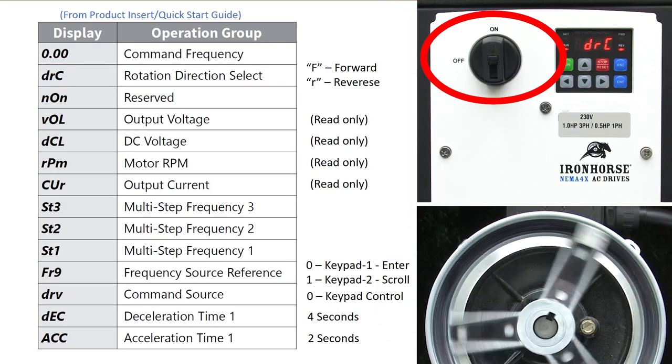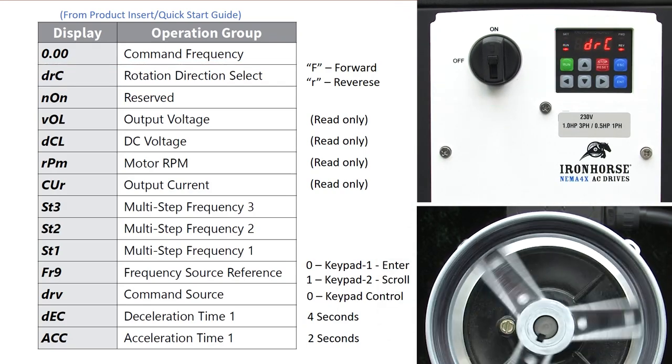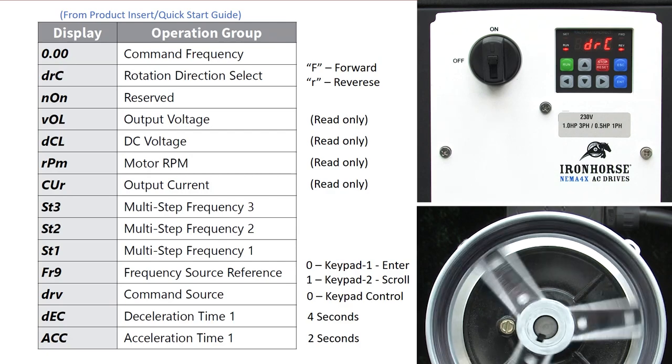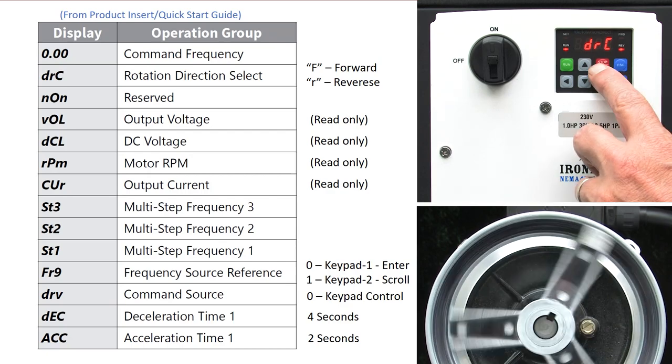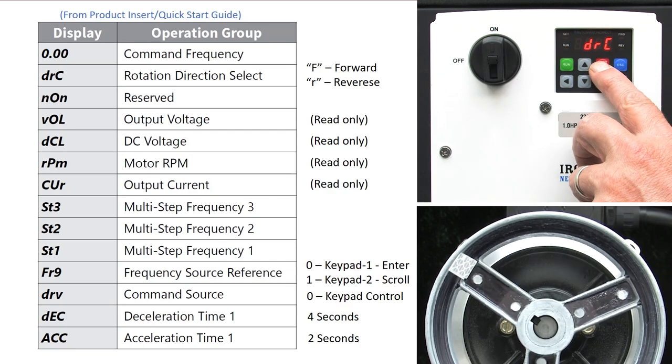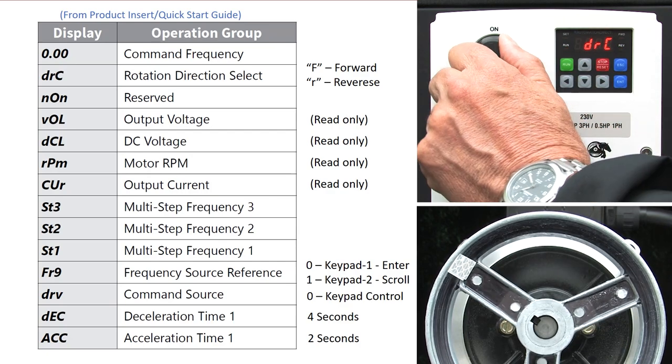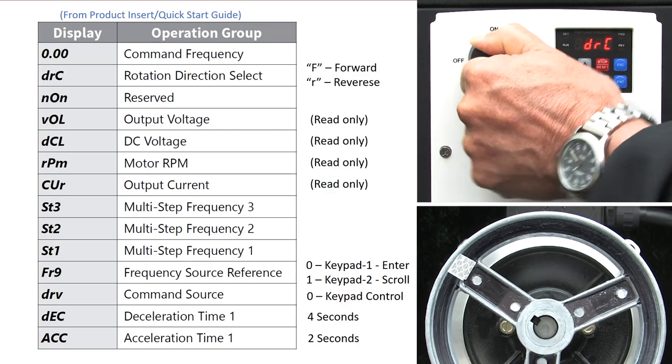While the built-in disconnect is handy, you should never use that to stop the motor. Always hit stop, wait for the motor to spin down, then remove power from the drive.